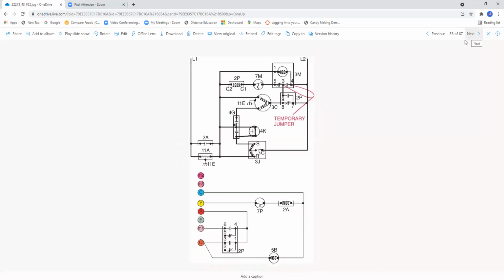Okay, now here's a temporary jumper applied to this diagram over here. So what's going on with this temporary jumper? When all else fails, install a temporary jumper. By the way, this is under service calls under air source heat pumps on page 1315. In this application, when the unit's off, the technician applies a jumper wire from terminal 3 to 4 to cause a defrost, to avoid having to wait for the timer.